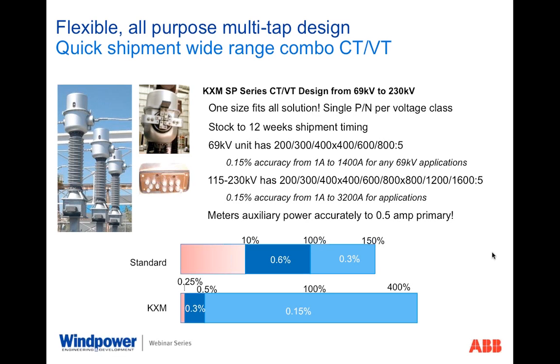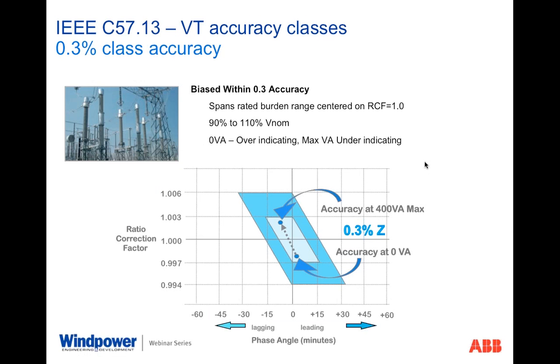So in this application, by using this wide range device with the 0.15 accuracy commitment over 0.5% to 400%, combining that with multi-taps, it's been a real important tool to be able to meter any installation. And you have one part number for a voltage class. So you don't have to worry about too many items that you have to inventory. So with that, now let's talk a little bit about the voltage transformers. We went from CTs to combined units. Now let's talk about the other side of it, and that's the voltage transformers.